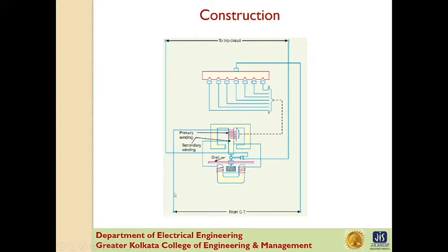The primary winding is connected to the secondary of a CT in the line to be protected and is tapped at intervals. The tappings are connected to a plug setting multiplier, plug setting bridge, by which the number of active turns of the relay operating can be varied, thereby giving the desired current setting.